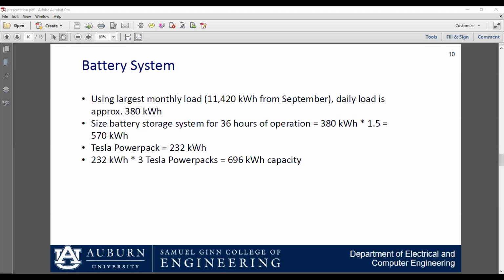So a battery system is needed to cope with the intermittent nature of a PV system and to also supply power to the microgrid when there is no power available from the power grid. So we use the largest monthly load from September. That was 11,420 kilowatt hours, divided by 30. The daily load is approximately 380 kilowatt hours, assuming a need of 36 hours of capacity, 1.5 days. So we assume that the battery storage minimum capacity is 570 kilowatt hours.